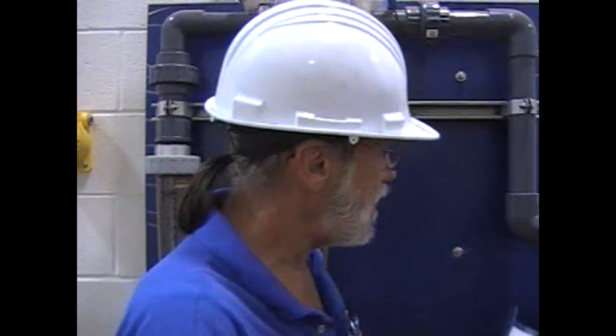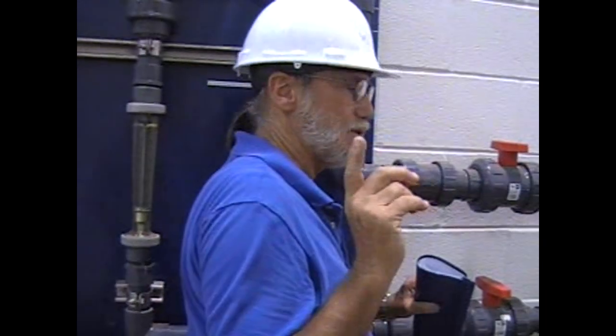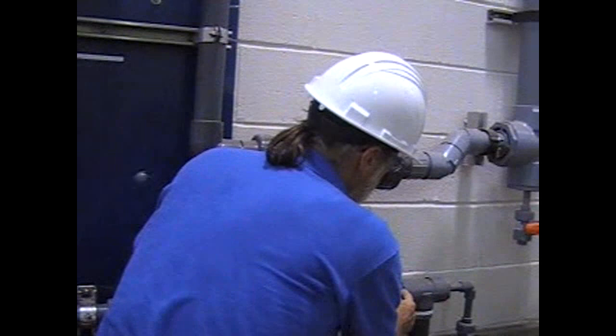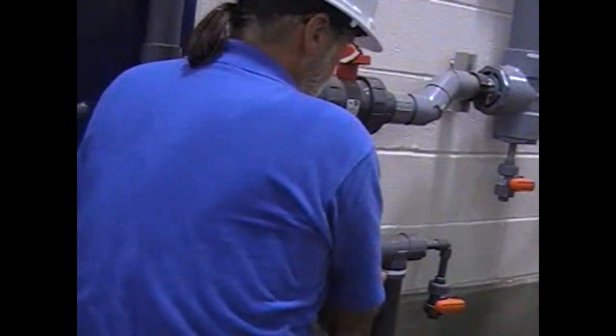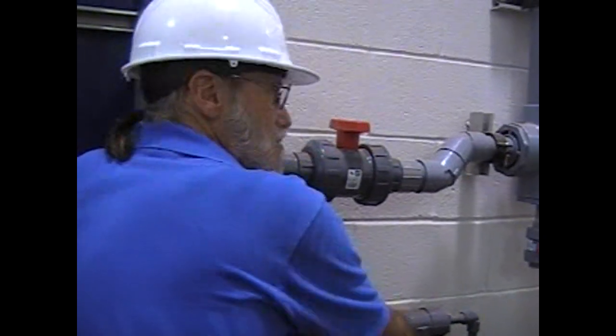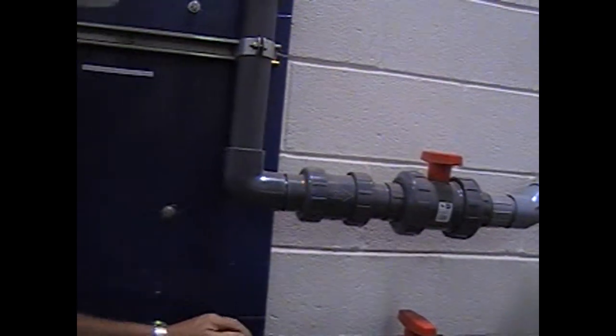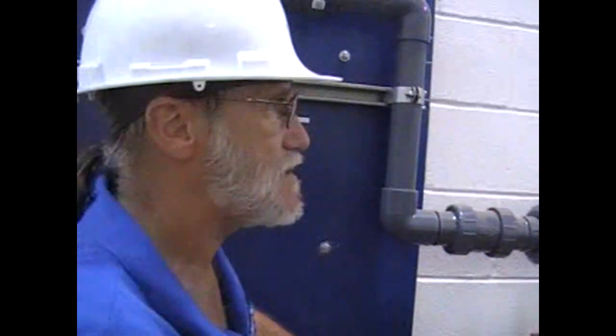Once the contractor was out of his plumbing guarantee, but then as time went on, this bleach and also the brine too, the salt too, it actually eat the glue away. The pipe wouldn't blow apart, but you see like snowballs, white snowballs, all the joints like that. And to go through and replace some of this plumbing is not real simple to replace.